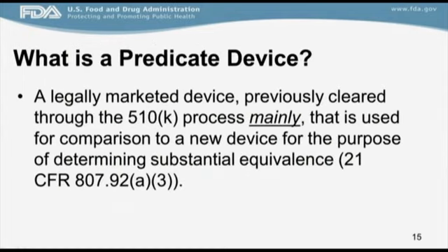So what is a predicate device? You are demonstrating substantial equivalence, so you have your new device and a predicate device. The predicate device is actually a legally marketed device that is typically cleared through the 510K process. And this is used for comparison of your device, the new device, to the predicate device. And this is the premise of substantial equivalence.